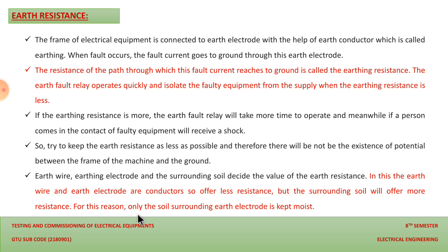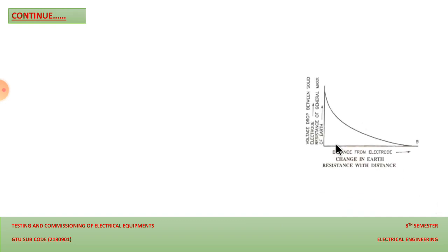So the soil surrounding the earth electrode is kept moist, so that we can reduce the earth resistance, and we can discharge that heavy charge whenever the fault occurs, and we will have a sudden operation of the earth fault relay, and we can remove our equipment from the electrical supply. So let us discuss how this soil resistance is the most important factor.